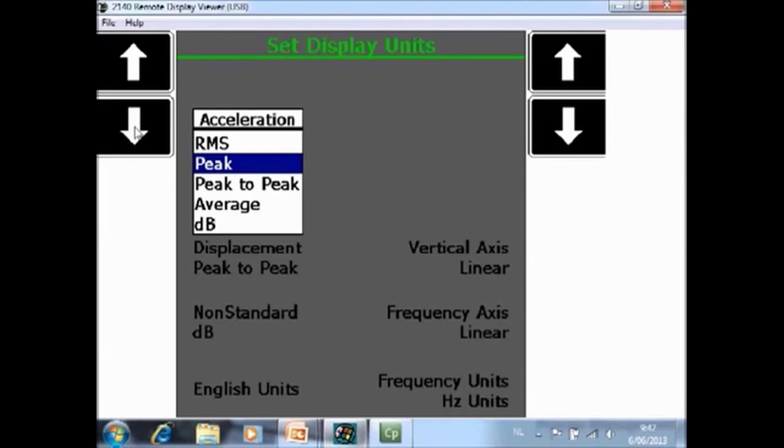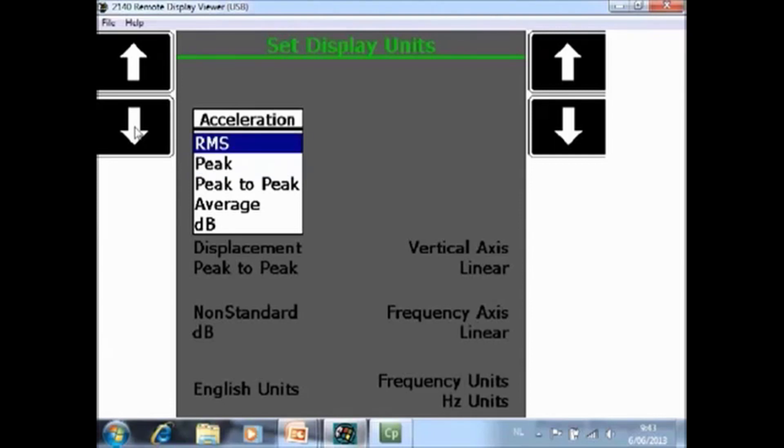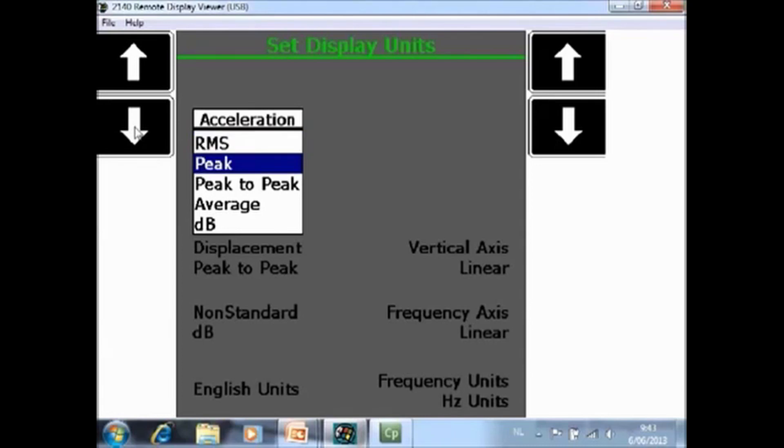An example, if all your settings were here in peak and you have collected already a lot of data, all the acceleration data will be explained in peak. However, if you go back to this screen and you put acceleration into RMS, all the historical data will be converted immediately and will be displayed in RMS.